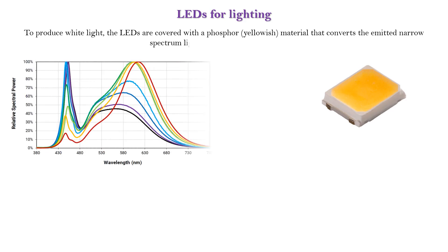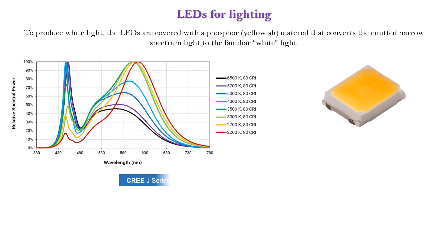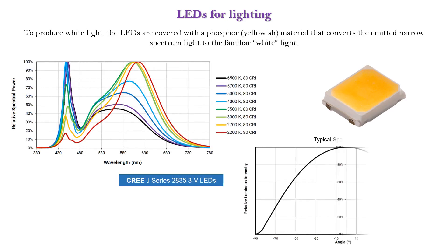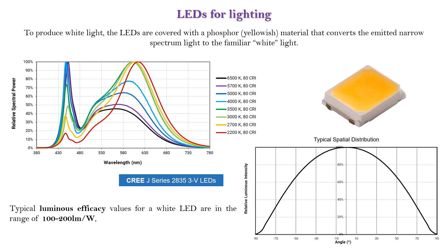To produce white light, the LEDs are covered with a phosphor — a yellowish material that converts the emitted narrow spectrum light to the familiar white light. Typical luminous efficacy values for a white LED are in the range of 100 to 200 lumens per watt, much higher compared to incandescent lamps and fluorescent tubes.